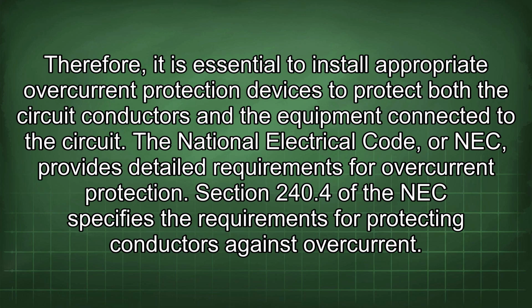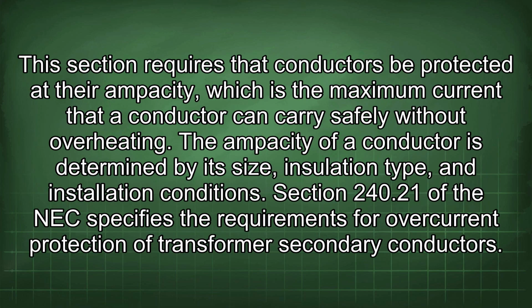Section 240.4 of the NEC specifies the requirements for protecting conductors against overcurrent. This section requires that conductors be protected at their ampacity, which is the maximum current that a conductor can carry safely without overheating. The ampacity of a conductor is determined by its size, insulation type, and installation conditions.